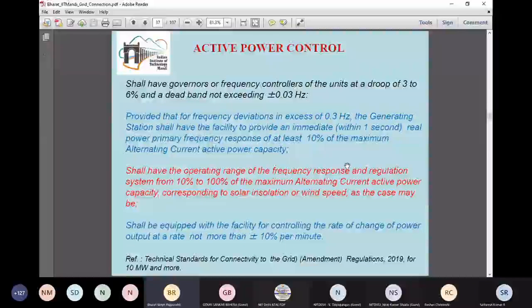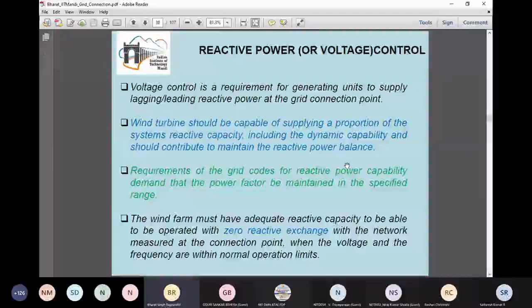Then next slide, please. This is known as the active power requirement or frequency control. Similarly, we also have reactive power or voltage control requirements. In this case, it is expected that the wind farm or solar farm or other renewable energy sources should be able to provide reactive power and absorb reactive power based on the grid connection requirements. But in a broad sense, it is expected that the wind farm or wind turbine should be able to maintain a zero reactive exchange with the grid.